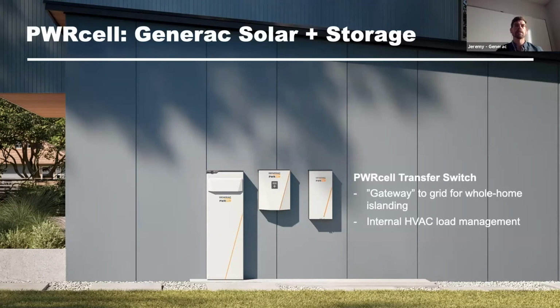Last but not least, this is the PWRcell transfer switch. In a whole home power configuration, this is the interface between your customers' electrical systems and the grid. When the grid goes down, this is what's actually isolating and islanding your client's home from the grid to keep all that energy that is stored and produced by the PWRcell on site. This is how we get up to 9 kilowatts of continuous power to the entire electrical panel in your client's home.